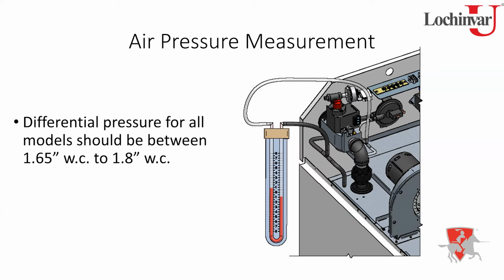Now, if the pressure on that burner tube goes positive, then your differential starts to shrink. So if I had a pressure of 1.5 inches in that front chamber, and then off that burner I had a positive pressure of 0.4 inches, my differential is now 1.1. I've got a problem because that switch isn't going to make.